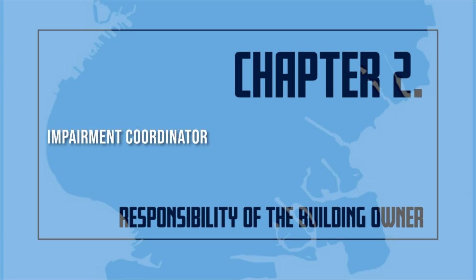Impairment coordinator. The building owner shall assign an impairment coordinator to comply with the requirements of this study material. The impairment coordinator shall take the actions when a standpipe system, sprinkler system, or fire alarm system is out of service. The impairment coordinator shall maintain records of all system inspections, tests, servicing, and other items of maintenance. These records shall be kept on the premises or other approved location for a minimum of 3 years. These records shall be made available for inspection by any member of the fire department. In the absence of a specific designee, the building owner shall be considered the impairment coordinator.